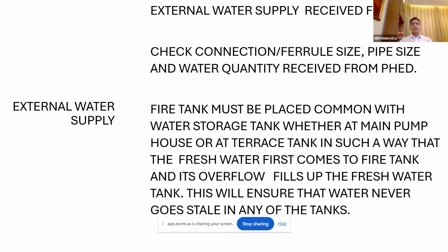A fire tank is an important safety precaution in a building. This fire tank should always be full. In case of fire, its water will be used to the full capacity. But I have to make sure that water in the fire tank does not become stale. After one week, this tank with water will start stinking. So what I do is bring my inlet connection into this fire tank. Overflow of the fire tank will go to my drinking water side. Drinking water is consumed every day, and every supply time water will come and ensure that water in the fire tank also remains fresh and doesn't stink.